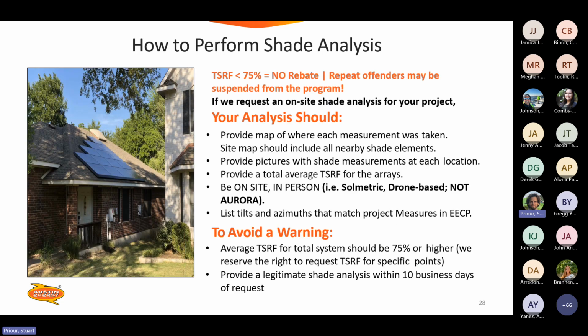So how to perform a shade analysis. Like we said, you need to have a total solar resource fraction of 75% or greater to get rebate funding. And your shade analysis should provide a map. So you've got to do this on site because you've got to be on the roof and you've got to provide photos at each location where the array is proposed to be set. You need to provide a total average resource fraction for the array or the arrays. You need to be on site and in person to do this.